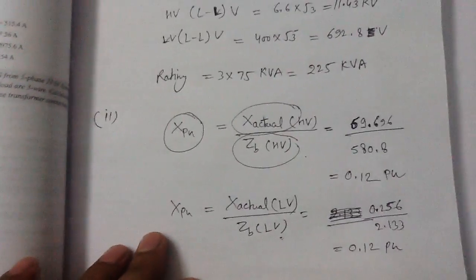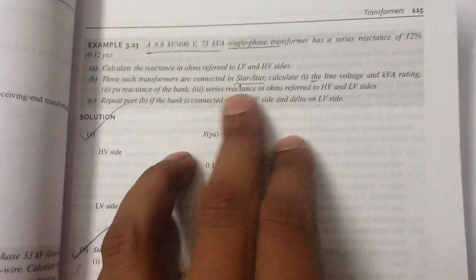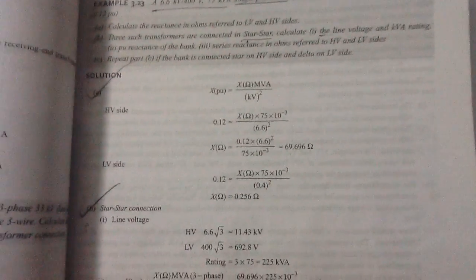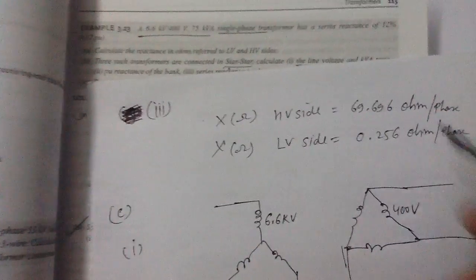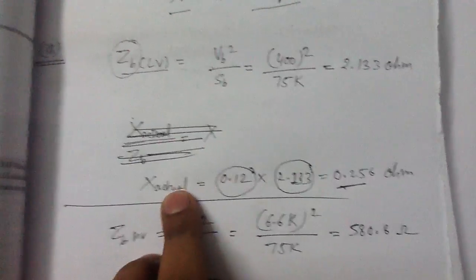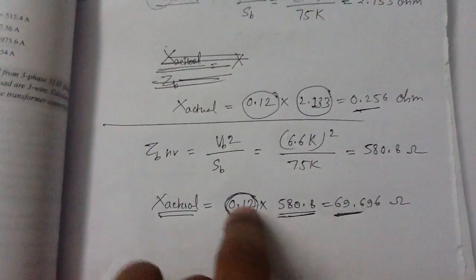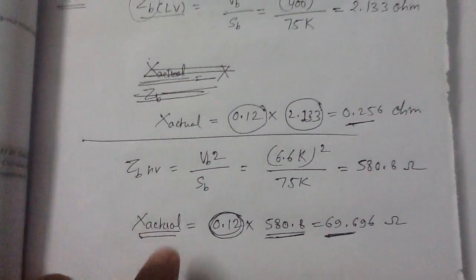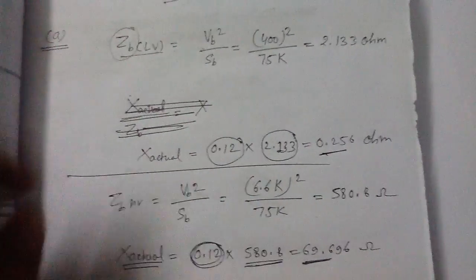In the third part of Part B, we are asked to find the series reactance in ohms referred to HV and LV side. The reactance values remain the same as calculated in Part A: X_actual referred to LV side is 0.256 ohm and X_actual referred to HV side is 69.696 ohm, regardless of whether the transformer is connected star-star, star-delta, or delta-delta.